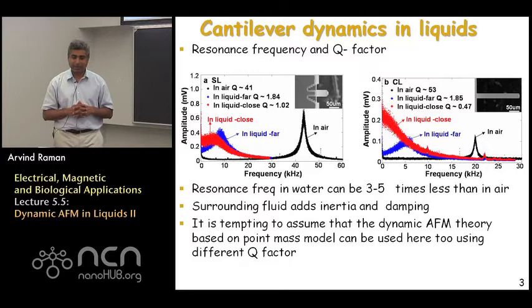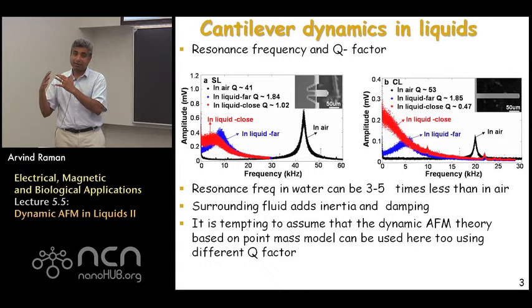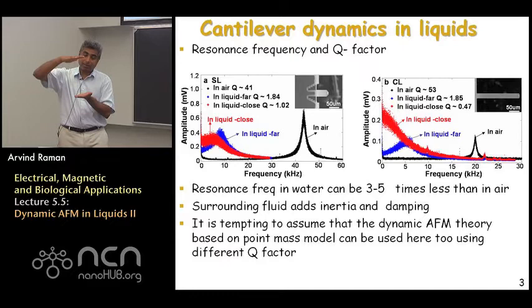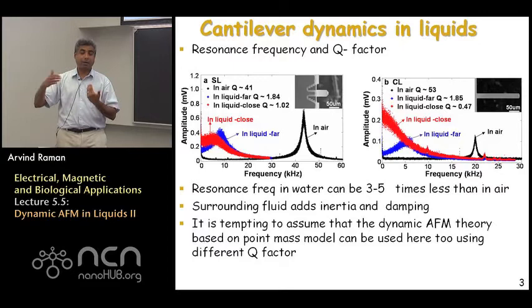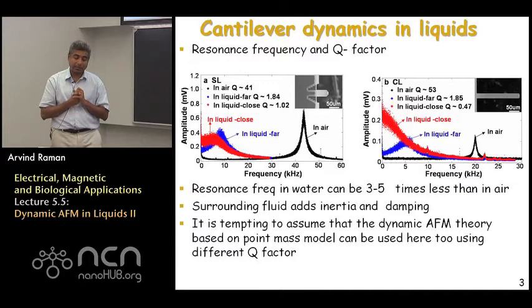Another interesting effect is that when you bring the cantilever close to a flat sample, the resonance frequency and Q factor change further. For example, what is shown in red is what happens to the Q factor and resonance frequency as you bring the cantilever close to the sample — the peak broadens even more and Q becomes less. Not as much as the difference between air and water, but there is a measurable difference between water far from a surface and close to a surface. This matters because you tune the cantilever far from the surface and then bring it close to image. These differences in Q factors and resonance frequencies are important especially for quantitative force reconstruction in liquids.